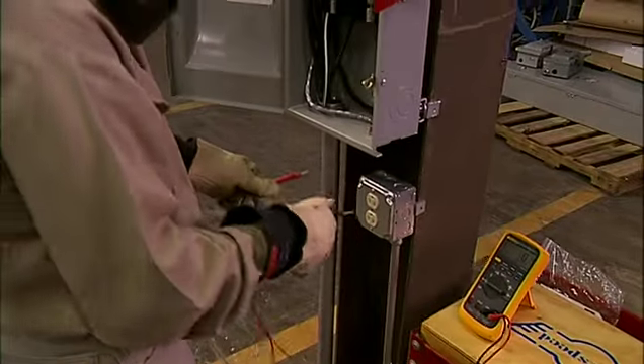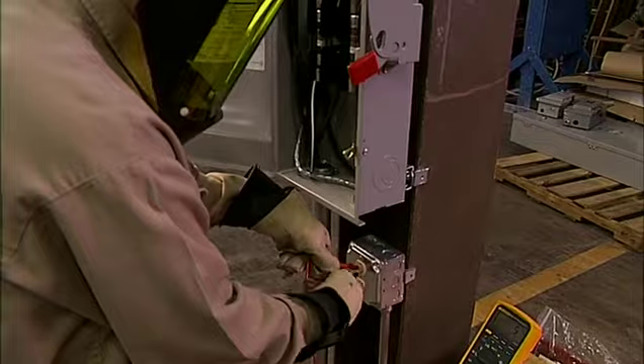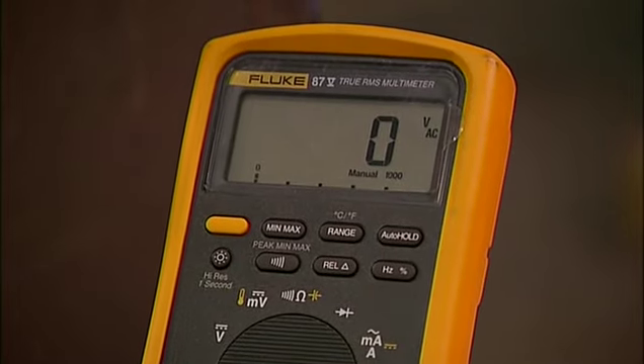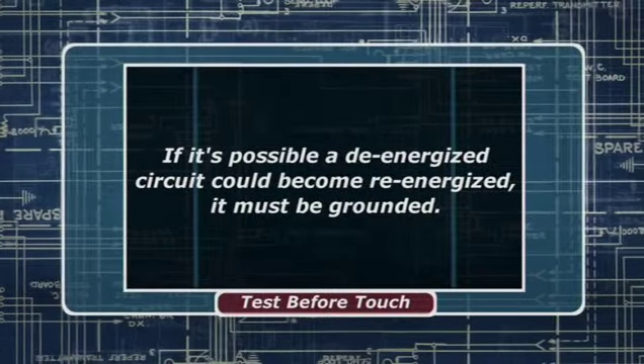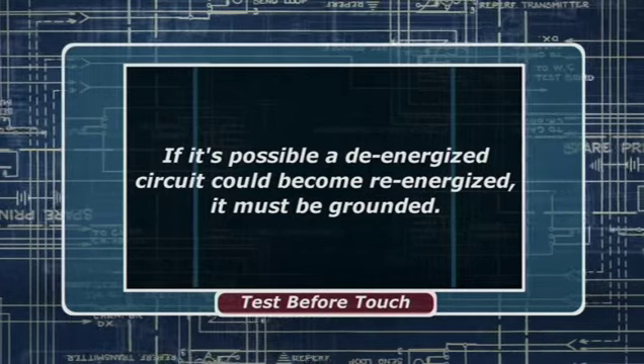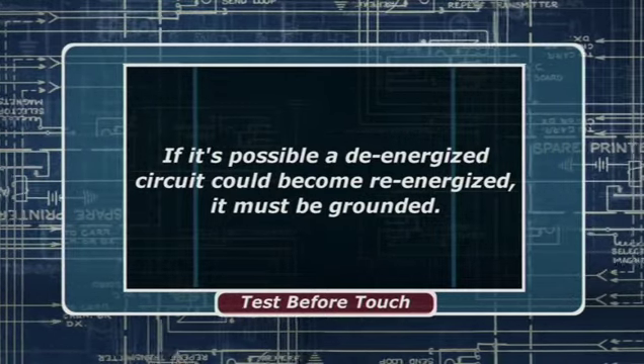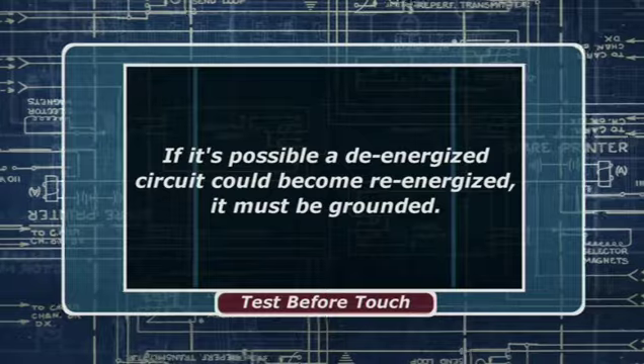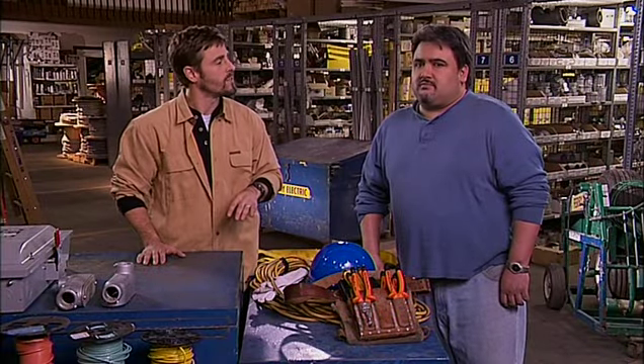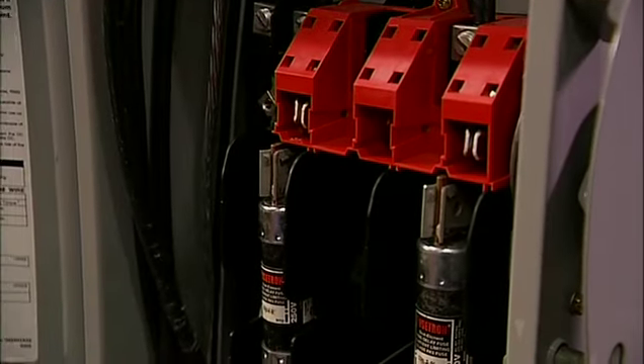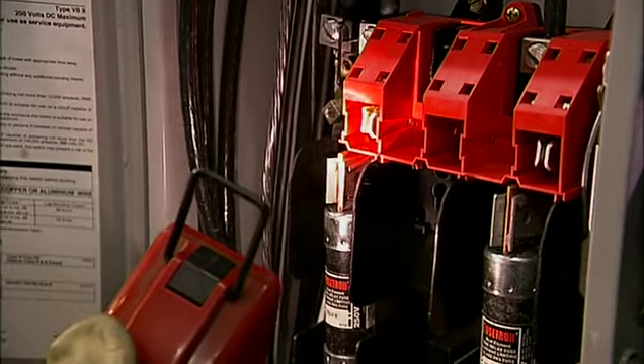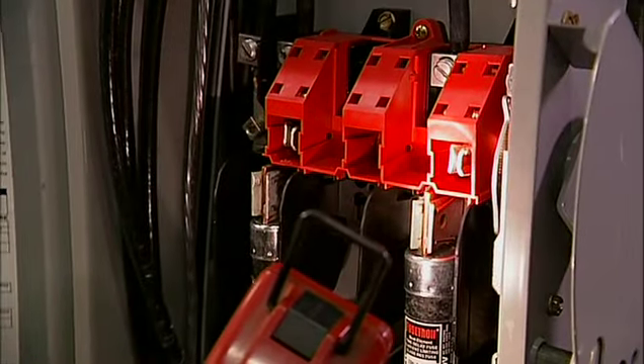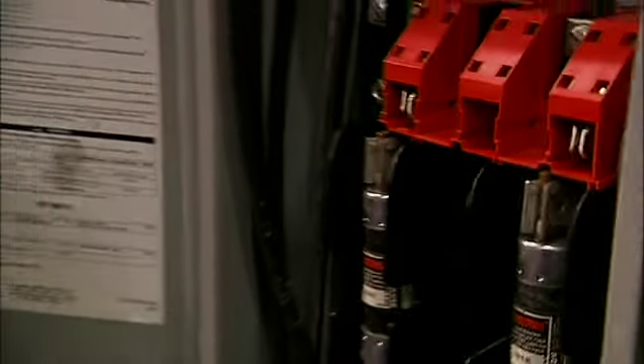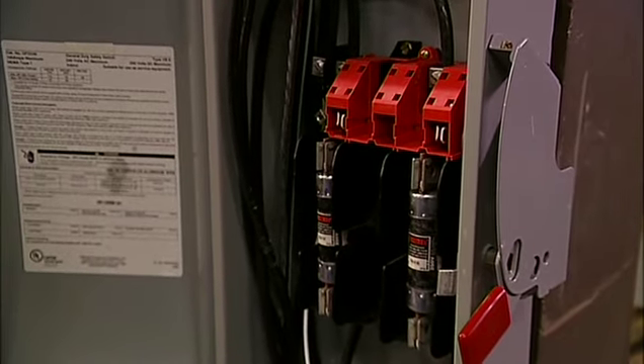That means break the connection to the source. Make sure there are no backfeeds. And if it's reasonably possible the de-energized circuits could become re-energized by another source, they must be grounded before you touch them. So what do you do after you remove the load from the circuit? Open the disconnecting device for each circuit. Way to go, Carl. And last, you got to visually verify that all blades of the disconnecting device are fully open, or that draw-out type circuit breakers are completely drawn out to the disconnect position.